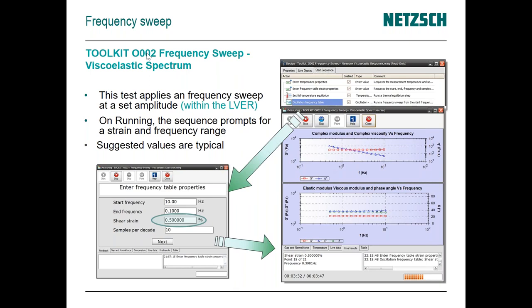Toolkit two allows you to perform a frequency sweep on your material — setting starting frequency, ending frequency, and strain. We discussed the linear viscoelastic region in part A — ideally this strain value should be within the LVR because any variation from being outside it will give very variable results. For dispersions like suspensions, foams, or highly particulate materials such as toothpaste, percent strain values will be very low, much less than one percent. For polymeric systems with very large molecules, strains can be much larger — from a tenth of a percent up to ten or twenty percent.